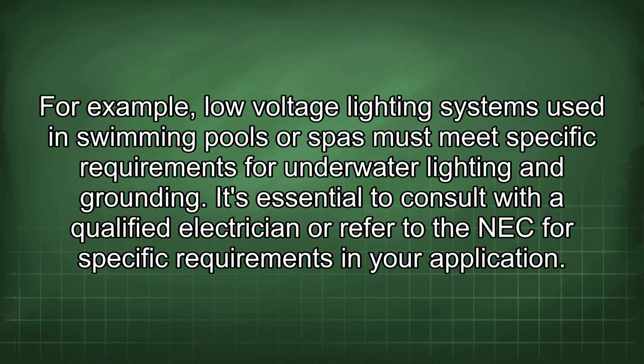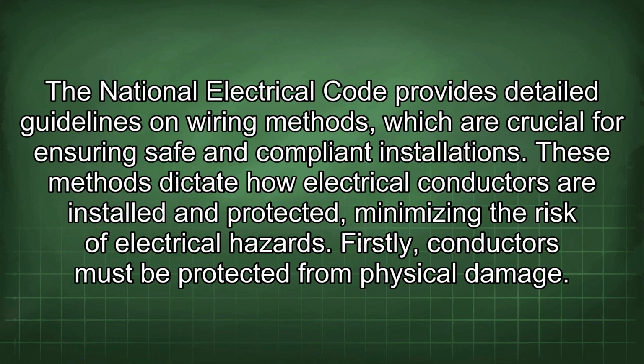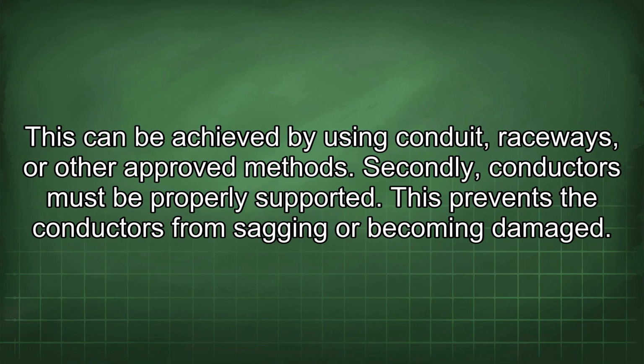The National Electrical Code provides detailed guidelines on wiring methods, which are crucial for ensuring safe and compliant installations. These methods dictate how electrical conductors are installed and protected, minimizing the risk of electrical hazards. Firstly, conductors must be protected from physical damage. This can be achieved by using conduit, raceways, or other approved methods. Secondly, conductors must be properly supported. This prevents the conductors from sagging or becoming damaged.